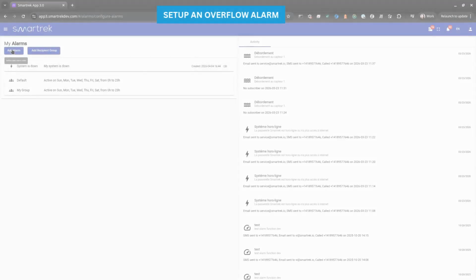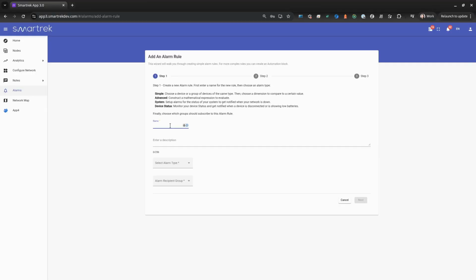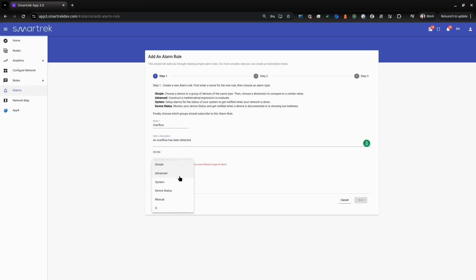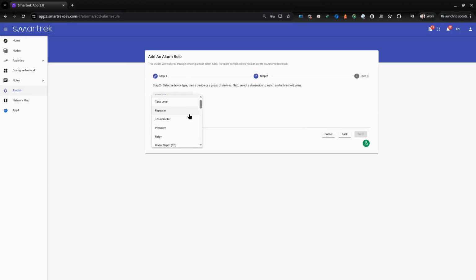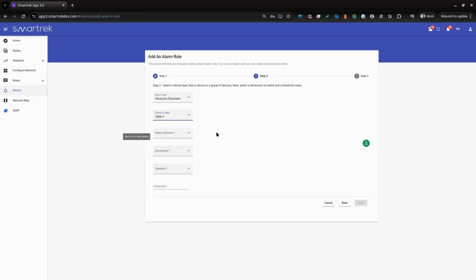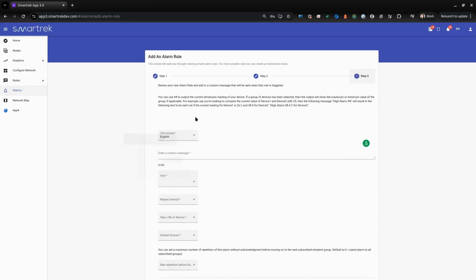Create an overflow alarm. Name your alarm, enter a description, then select the simple alarm type. Then, select your subscriber group. Choose the sensor type, ultrasonic flow meter. Choose the table corresponding to your system, then select the sensor to monitor, then select an alarm based on the water level measurement. Enter the level that should trigger the alarm.